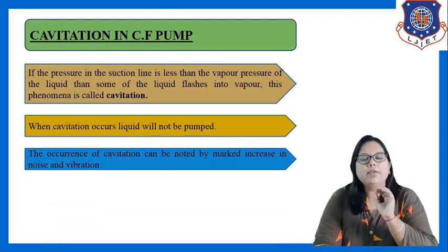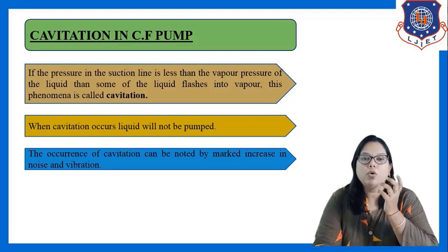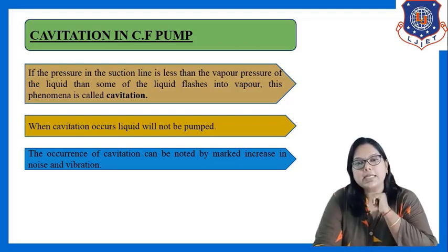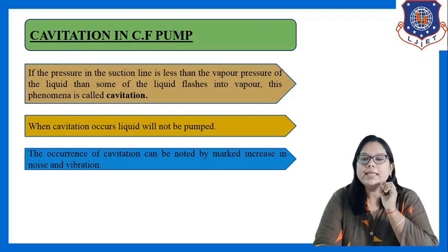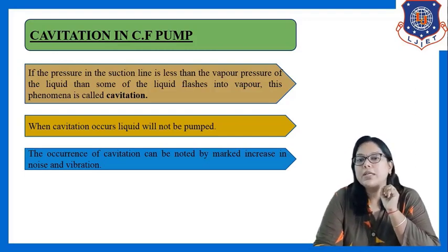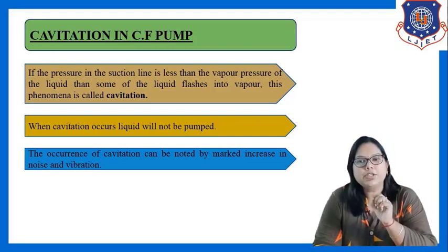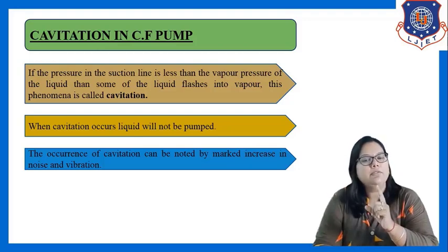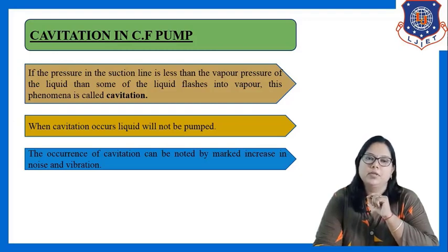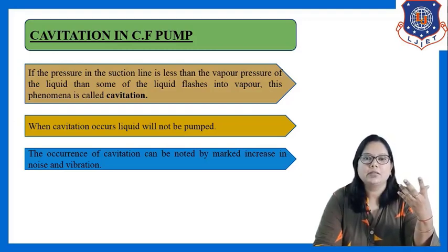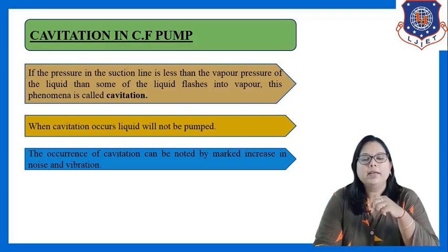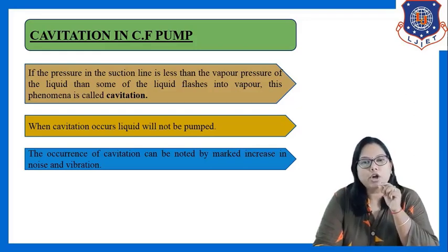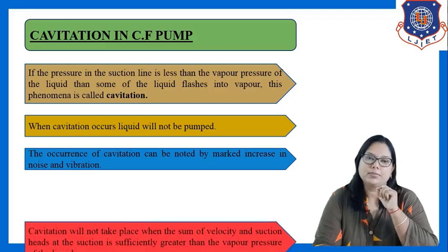The occurrence of cavitation, how can we know that cavitation has started? There are symptoms of cavitation. Now what are those? The occurrence of cavitation can be noted by a marked increase in noise and vibration. When cavitation starts, the pump gives noise and vibration. The noise of the pump increases, vibration increases when cavitation starts. So it is the notification of cavitation.